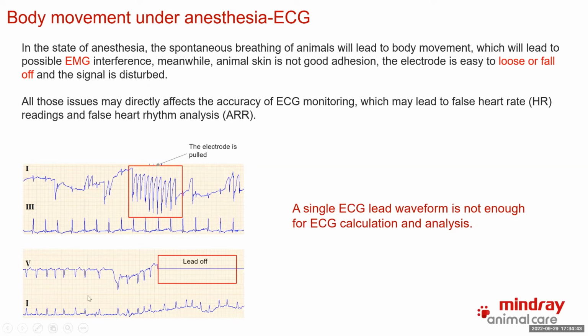You can see from the picture on the left side, on lead one right now, the electrode is being pulled. So you can see the waveform is having a lot of interference. Or maybe the lead is off, so the line will be a straight line. There's no signal there. Right now in the market, a lot of monitor products do the ECG monitoring based on only one ECG waveform. If this kind of situation happens, especially for the vet, because they very easily get some interference, a single ECG lead waveform is not enough to do a very accurate ECG calculation and analysis.